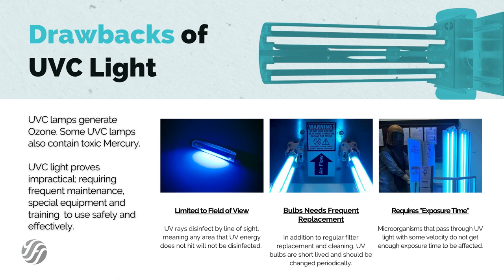Microorganisms that pass through UV light with some velocity may not get enough exposure time to be affected. So here again, the efficacy is questionable and certainly cannot make the claim of air sterilization.